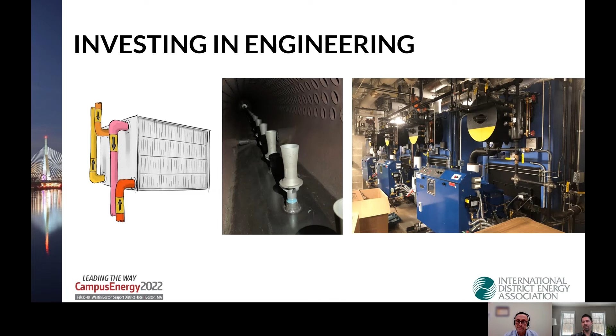The third example is the process load we had, with a high pressure steam system. There's no real efficient way to transform that, you're not going to install a gas unit just to get rid of steam. It's better to find a better way of producing it. So we installed high pressure steam boilers, but also engineered a system to recover heat from the stack. We've got four high pressure steam boilers operating right now at the efficiency of a hot water boiler, because we connected the heat recovery system into our hot water loop, increasing the whole campus efficiency at the same time. That's what investing in engineering meant for us.